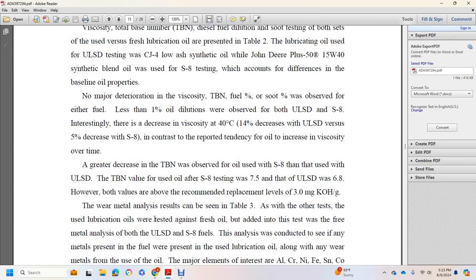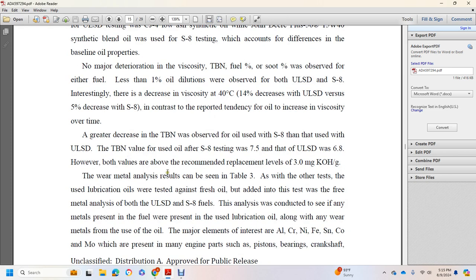A greater decrease in the total base number was observed with the oil used in the S8 than with the ultra-low sulfur diesel. The total base number value was 7.5 after the S8 testing and 6.8 with the ultra-low sulfur diesel. However, both values are above the recommended oil replacement level of 3.0 milligrams KOH per gram.